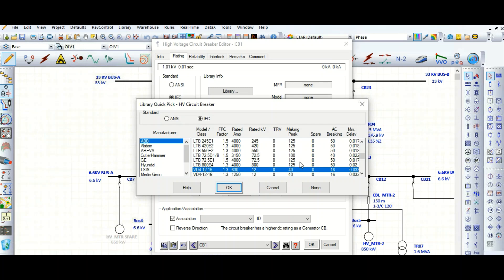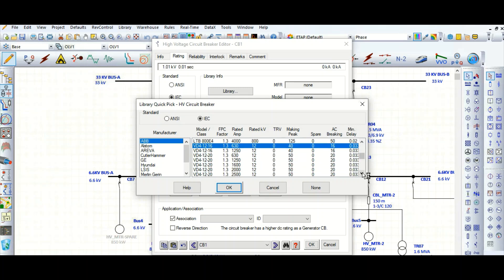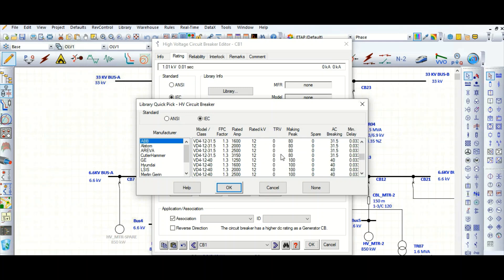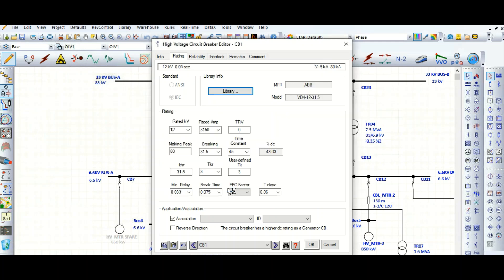Let's select the VD4-12-16. Here, 12 means the rated voltage is 12 kV, and 16 is the AC breaking capacity. For an 11 kV system, you can use this breaker — rated 12 kV, making peak 80 kA. Let's select it and I will explain the parameters.